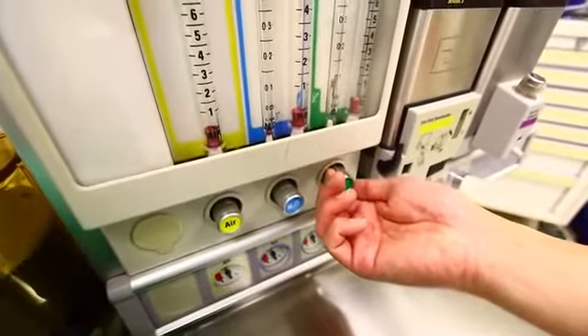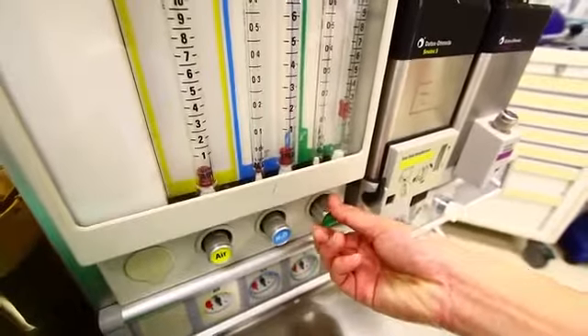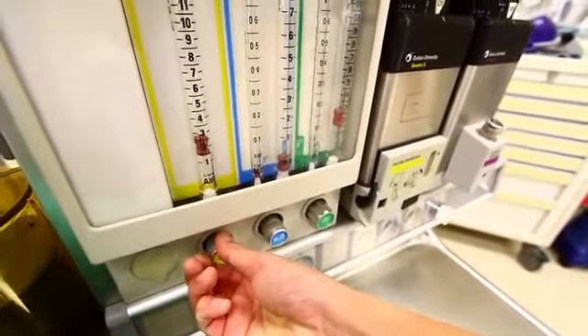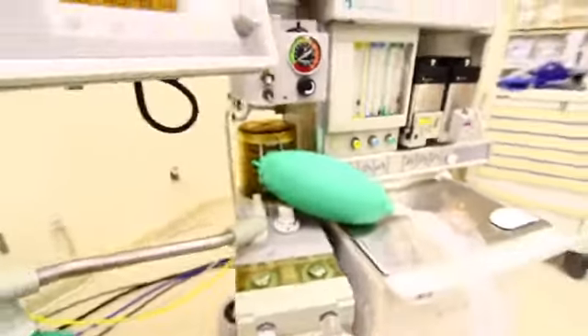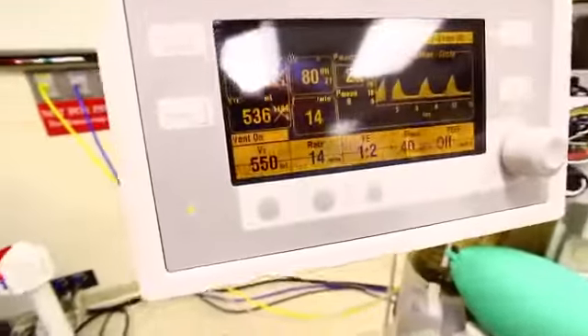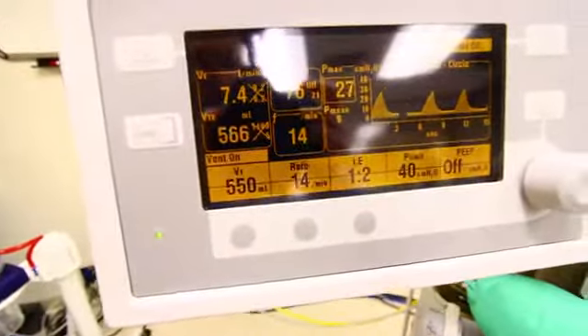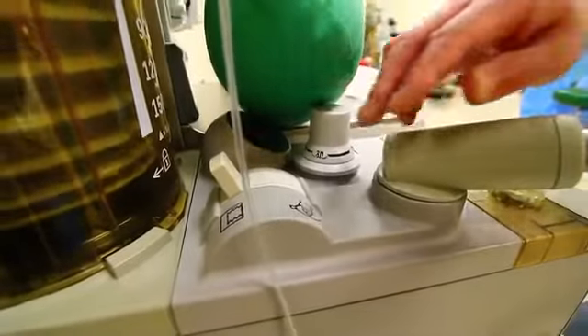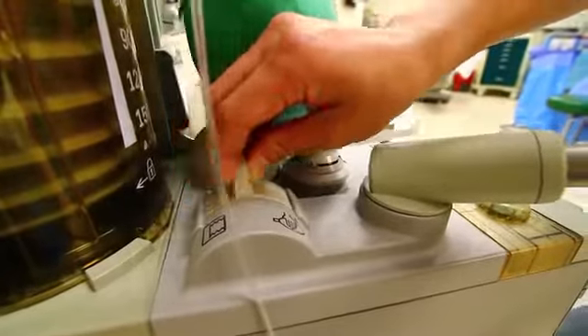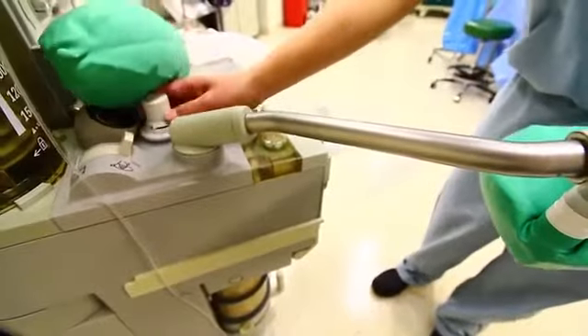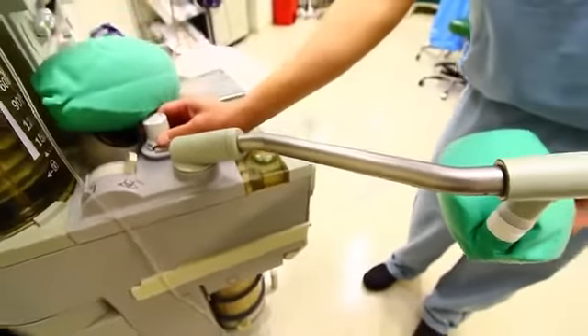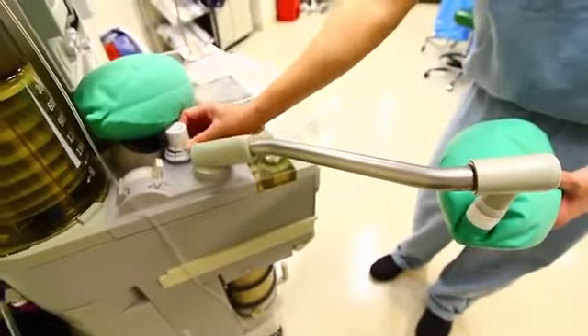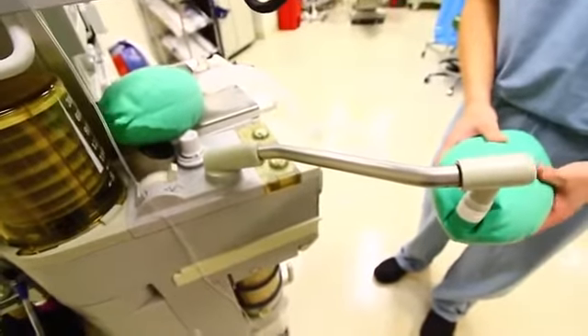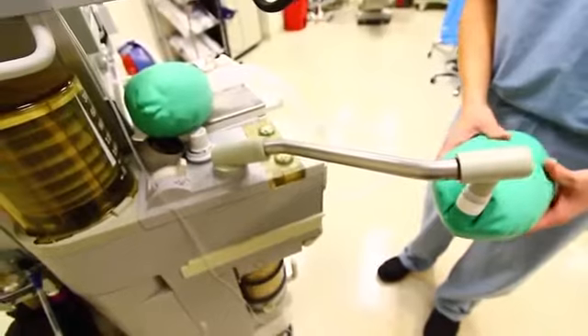Now set your fresh gas flows to about 5 liters per minute and ensure that proper tidal volumes are being delivered. Now you want to switch the ventilator back to the bag mode. Adjust the APL valve and ventilate manually and assure inflation and deflation of the artificial lung and appropriate feel of the system resistance and compliance.